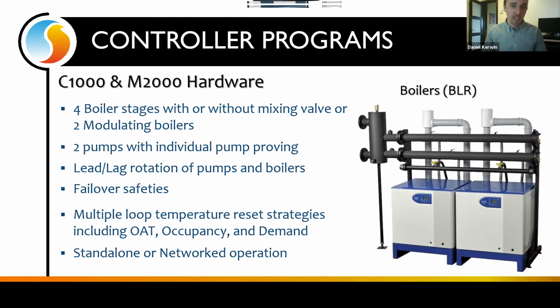And in terms of the control strategies, we can either maintain a fixed set point, or we can reset it based off of outside air, or perhaps based off of occupancy. Now, this controller is not to replace internal controls of boilers, but it's more to enable and disable boilers and then let the internal factory controls take care of the rest.